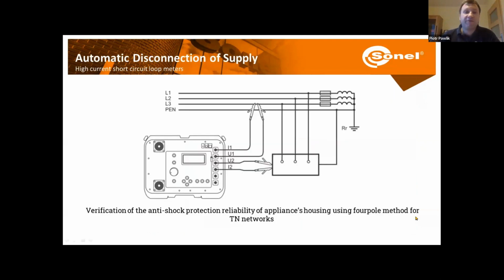And what's so special about them? Well, they use a high measuring current, and they also use a 4-pole method, thanks to which we don't need to worry about the resistance of the test leads. We can just connect directly here between the phase and ground channel and perform the measurement.